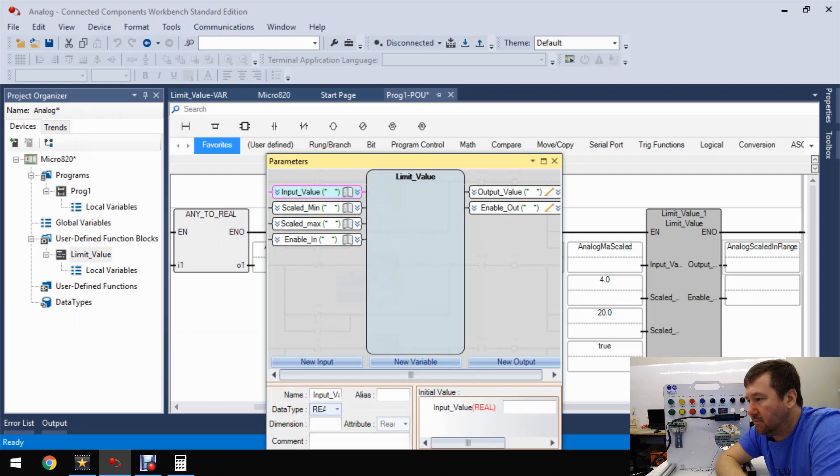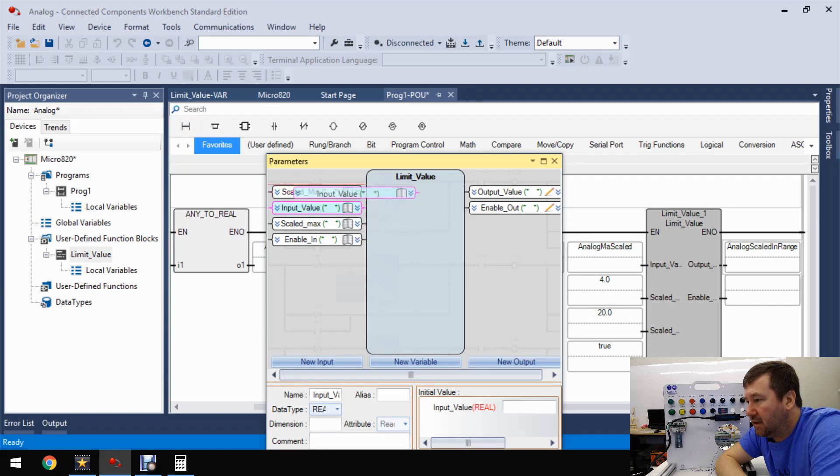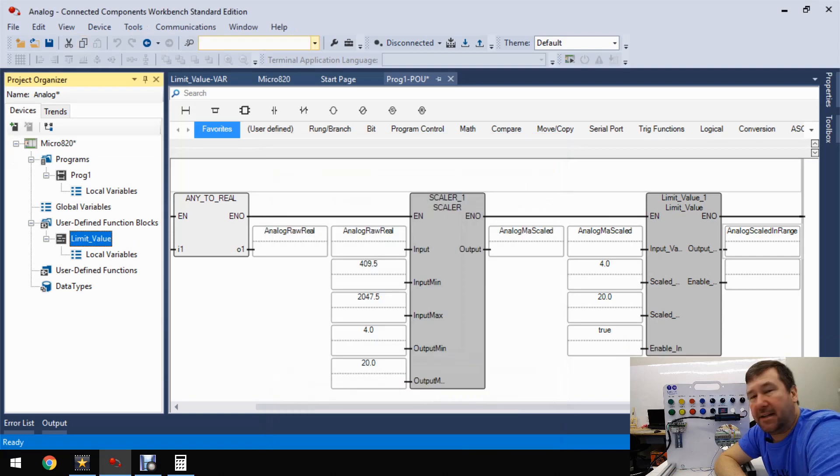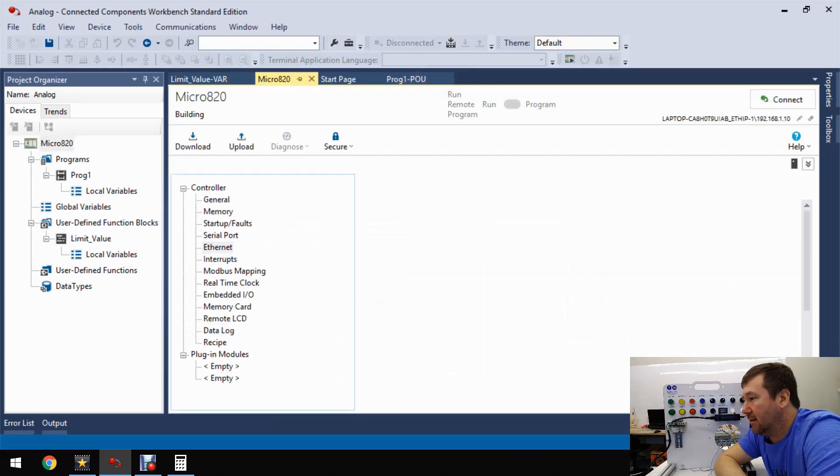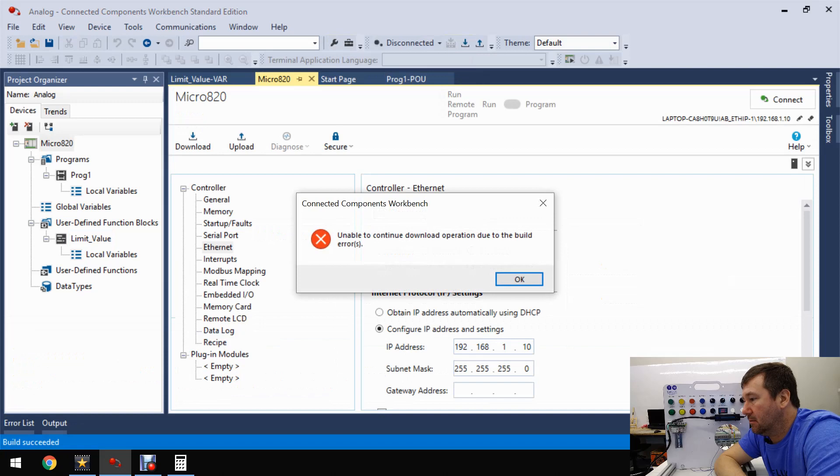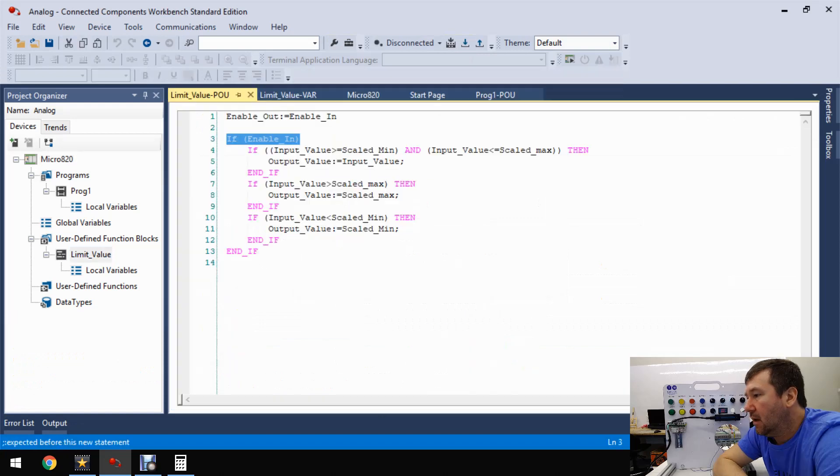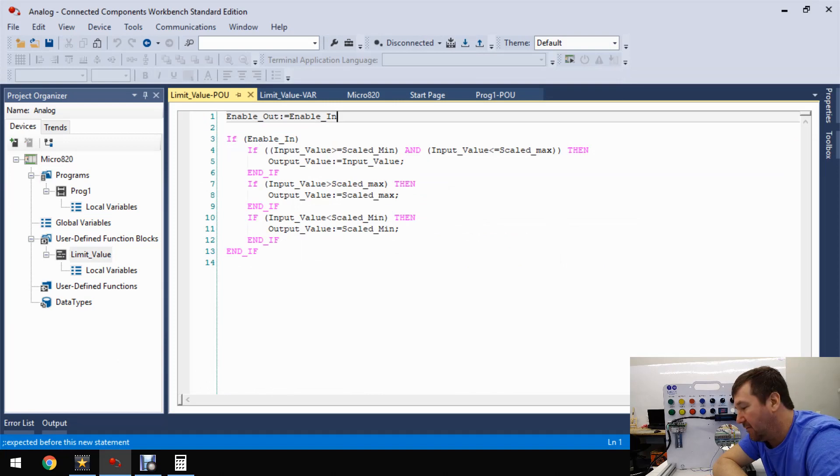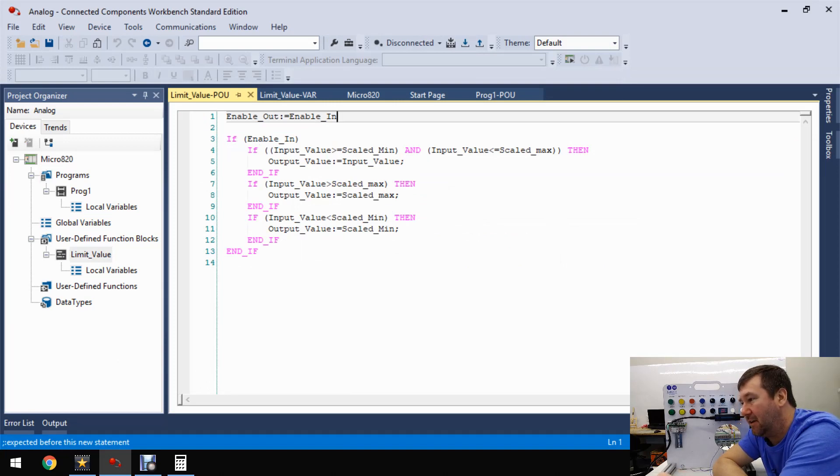To our input value, we're going to make this analog milliamp scaled. And then our minimum, we're going to make 4.0. Our scaled max is going to be 20.0. And then we have the enable in, and right now we're just going to make it true. And then we're going to have an output off of this. So let's just make this analog scaled in range real. And that's it. Also, let's just look at a few other things on this user-defined function block. Mainly, let's say we didn't like the order that these were in. If you go to parameters here, then you can actually change the order of these. You can just click them, drag them around. Now I like the order they're in, but as you're tightening them up, you might decide you like that. So let's go ahead and download that and see how it works.